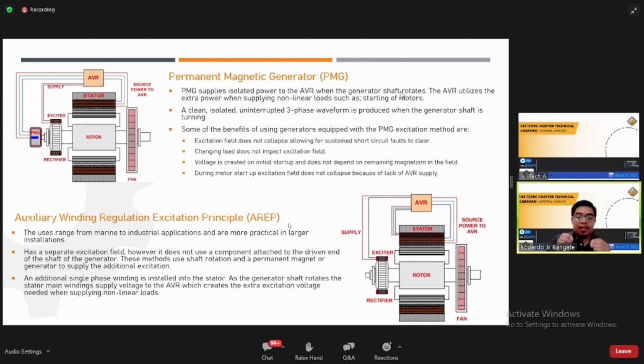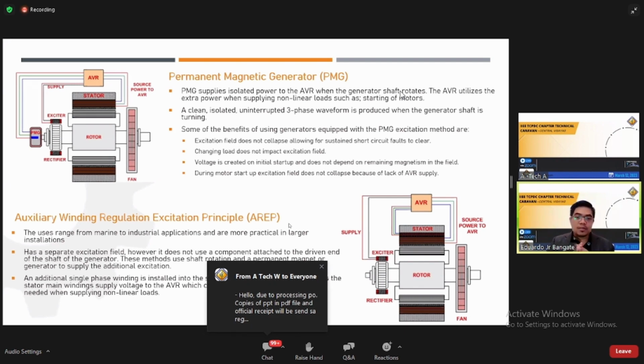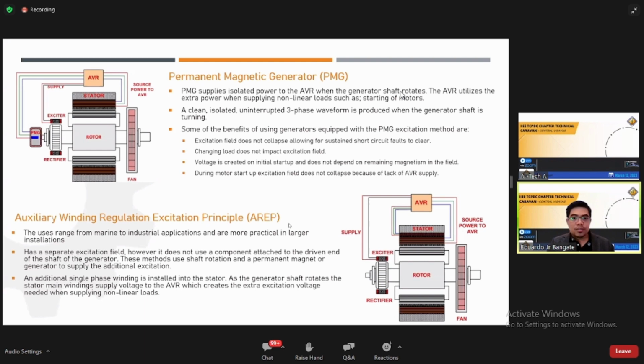Again, in our shunt type, we get the voltage from the main winding, the triggering voltage we mentioned earlier. But here, we have the permanent magnet generator that supplies the needed voltage for the AVR to operate at its peak level. Okay? Auxiliary winding regulation excitation principle, or AREP.